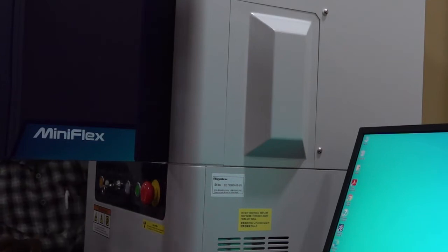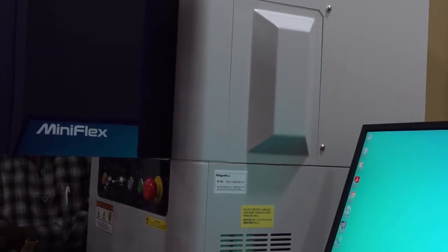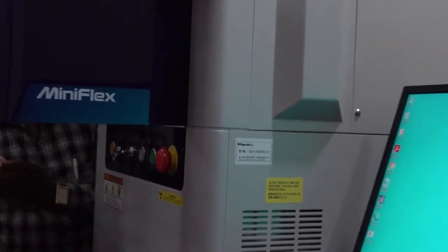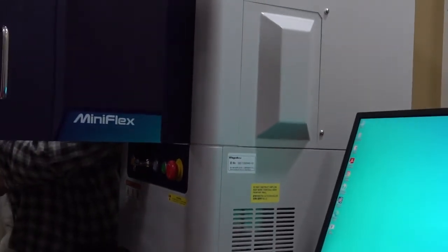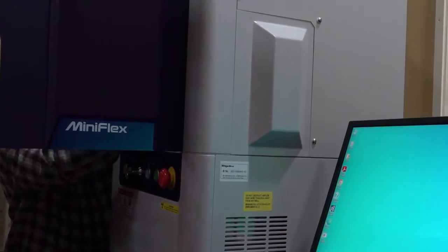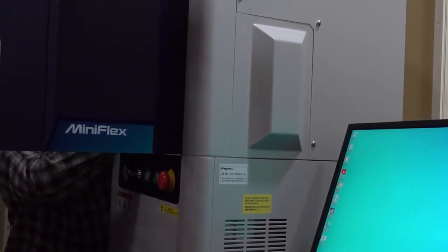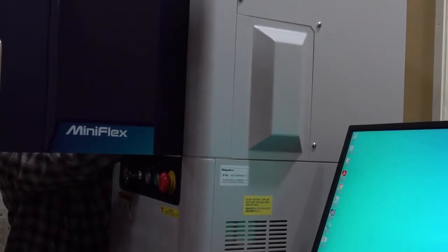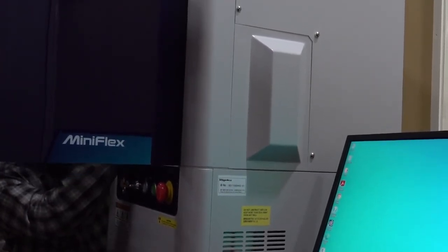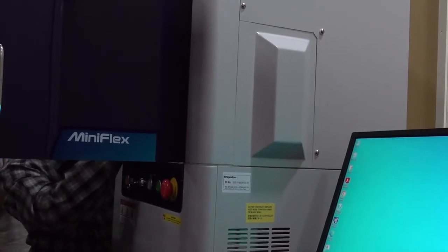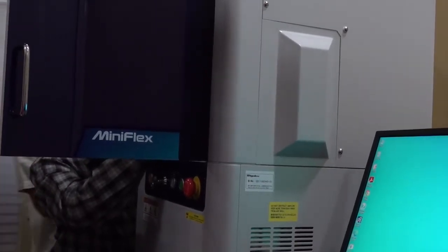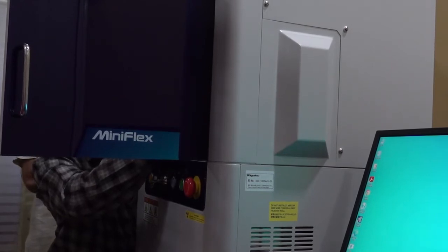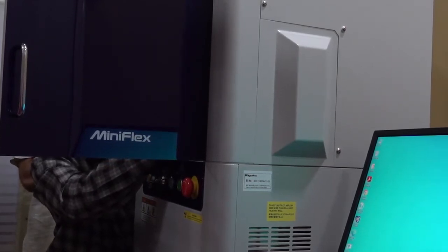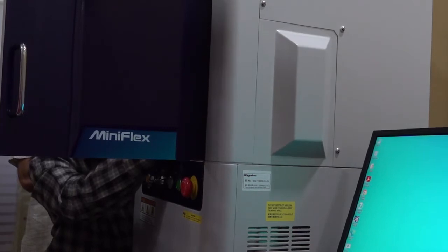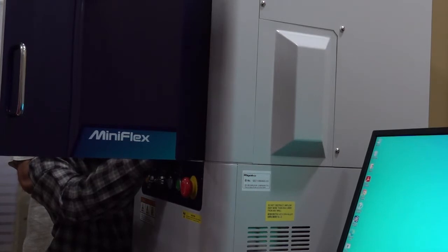So here we prepared one sample. This is a standard silicon powder. Okay, we have to keep it like this. So X-ray will come out from this window. It will fall on this sample and it will diffract and go to the Soller slit. Here the detector is there. This one is a semiconductor detector. It is a very fast detector. This can go up to 100 degrees per minute scan speed.